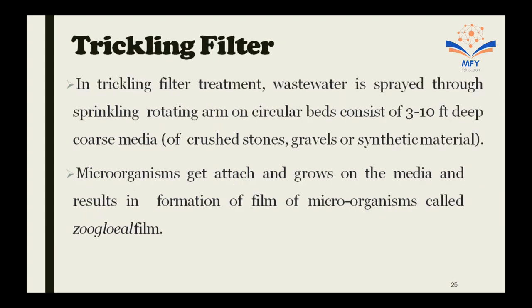Now, trickling filters. In trickling filter treatment, wastewater is sprayed through a sprinkling rotating arm on circular beds consisting of 3 to 10 feet deep coarse media of crushed stones, gravels, or synthetic material. Microorganisms get attached and grow on the media, resulting in the formation of a film of microorganisms called zoogloeal film. This film consists of millions of microorganisms that break down organic materials of effluent into simple and soluble matter. Treated effluent is drained at the bottom, where it is collected, then undergoes sedimentation in the SST. It is simple to operate and gives almost 80 to 90% BOD removal with high quality effluent.